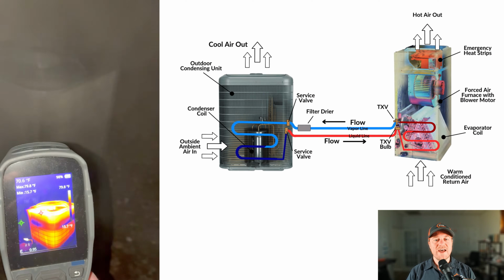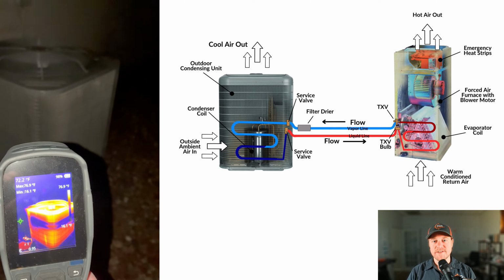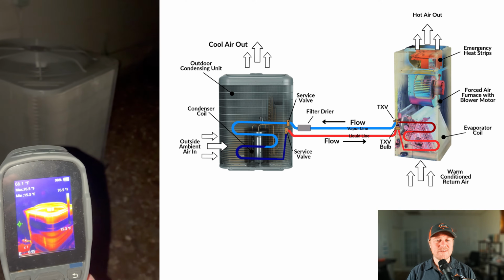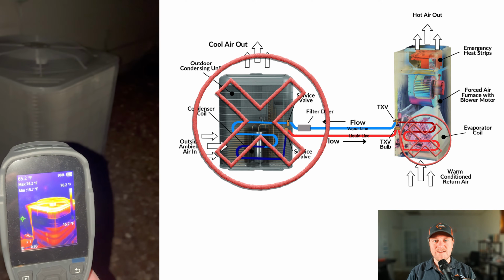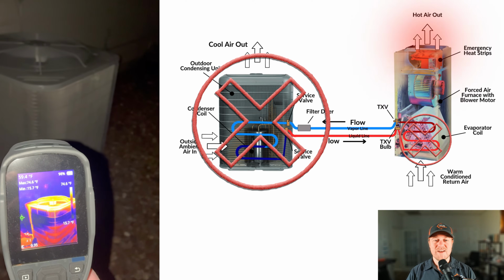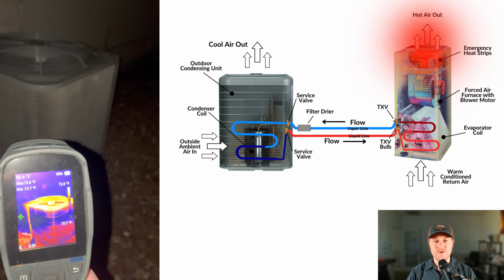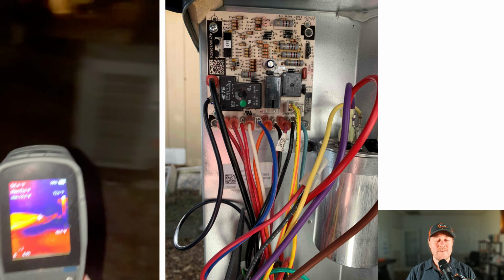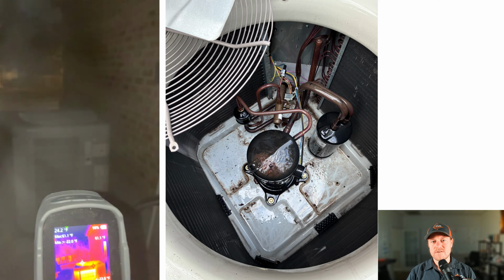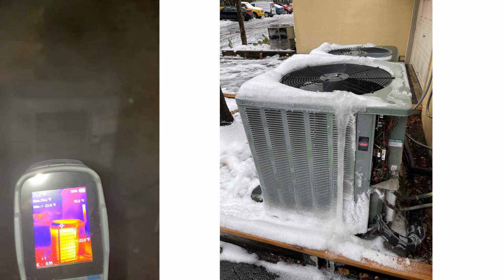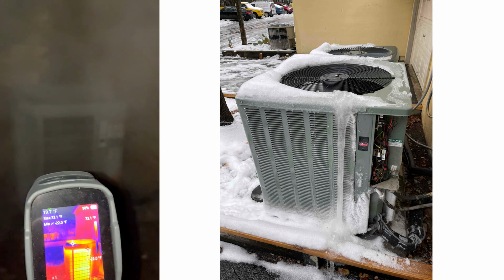Now this brings us to our last type of heating, which is emergency heat. Emergency heat is when the system does not use the heat pump at all to heat, only the heat kits. This can occur if you're having issues with your outdoor unit, like a faulty defrost board, or having issues with your compressor, and so on. The other reason why emergency heat could be needed is if the outdoor temperatures are just too cold for it to continue working. In that case, it's going to use the heat kits to get you through the cold snap. Basically, it's there to cover you for the worst case situation and buy you a little bit of time.